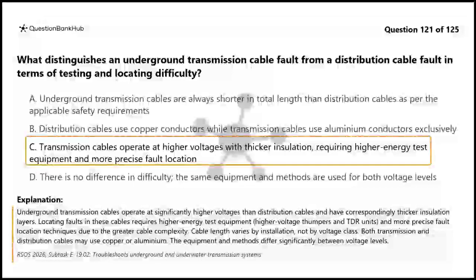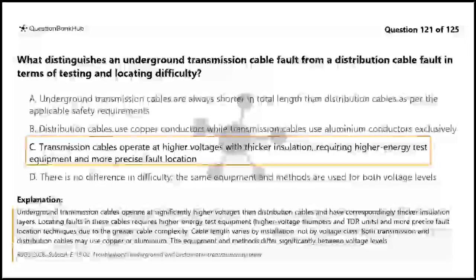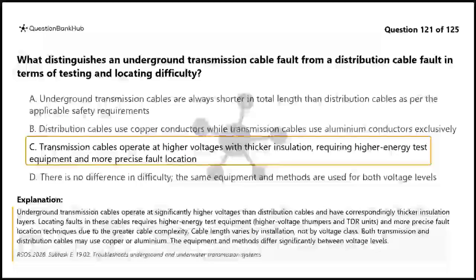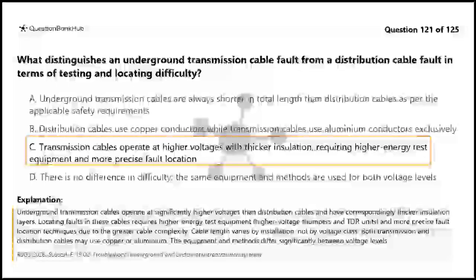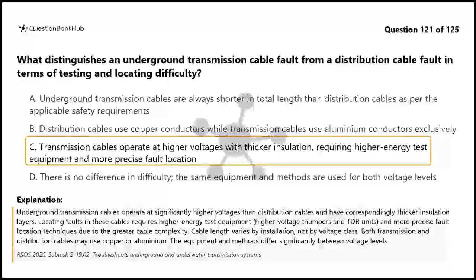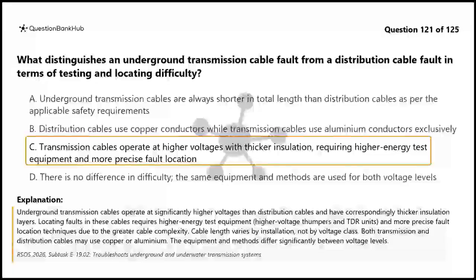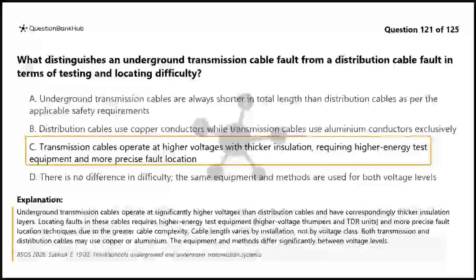Underground transmission cables operate at significantly higher voltages than distribution cables and have correspondingly thicker insulation layers. Locating faults in these cables requires higher energy test equipment, higher voltage thumpers and TDR units, and more precise fault location techniques due to the greater cable complexity. Cable length varies by installation, not by voltage class. Both transmission and distribution cables may use copper or aluminum. The equipment and methods differ significantly between voltage levels.